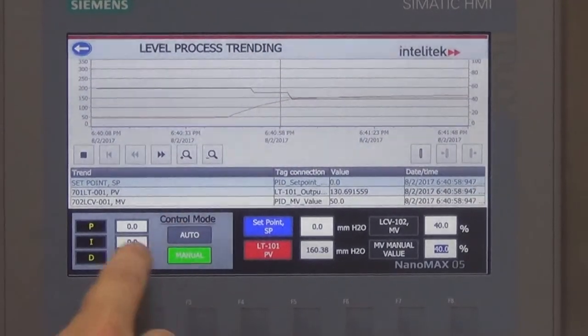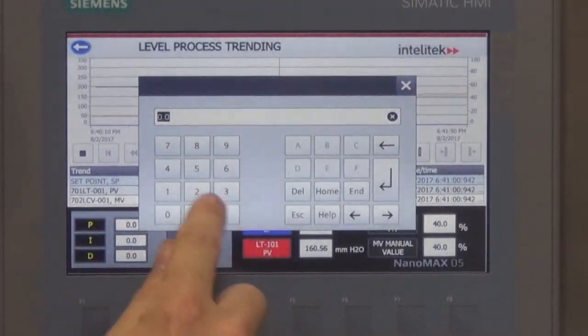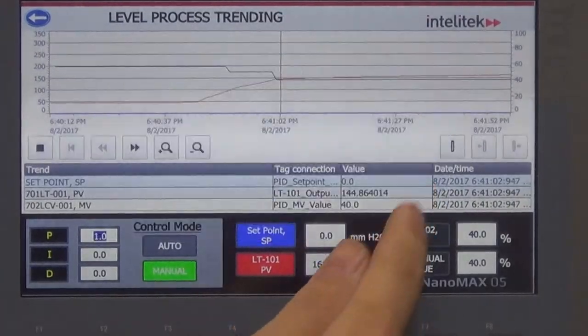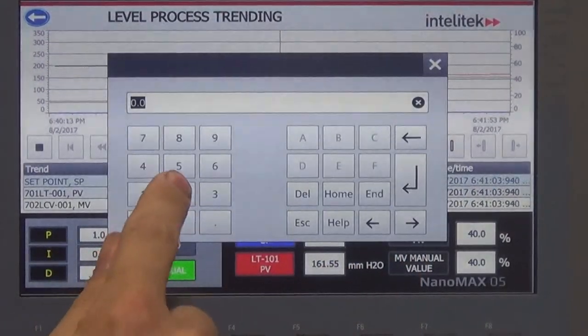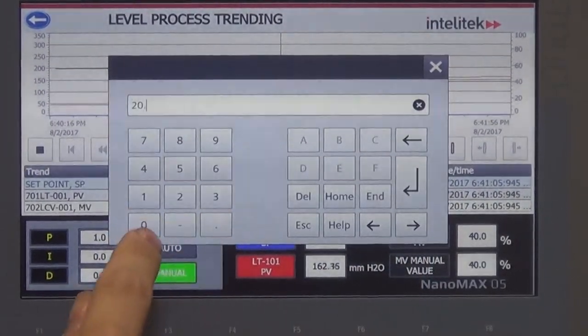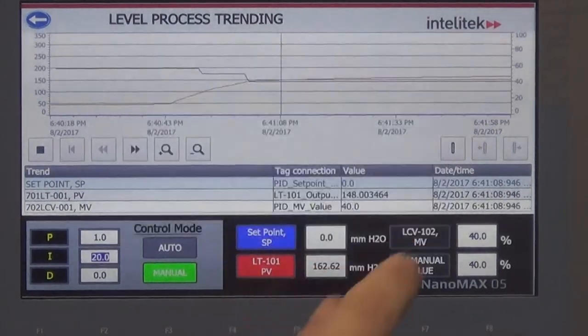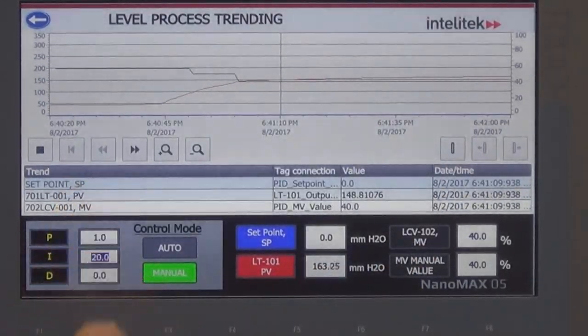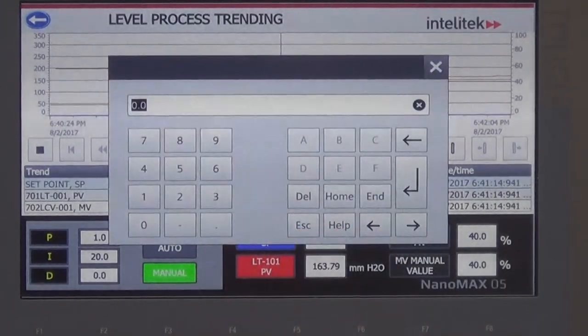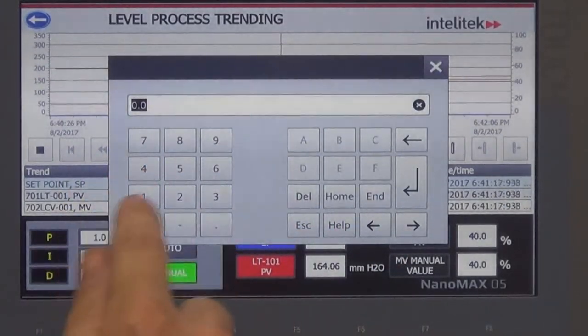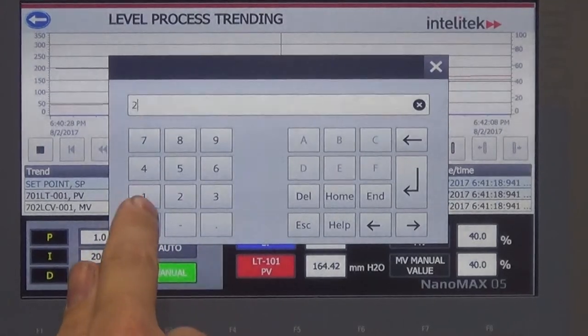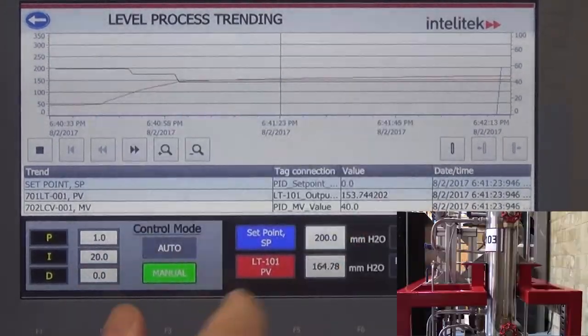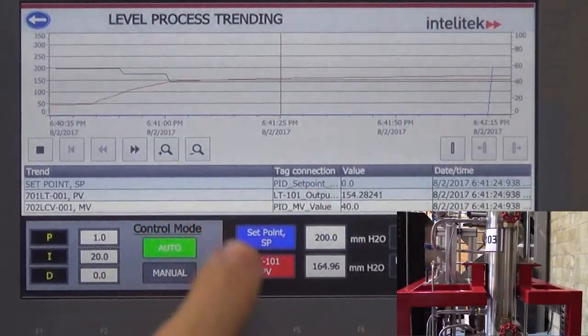And I'm going to type in P, so I'm going to put a value of 1. These are pre-tested values. I have all these values preset in the curriculum. And I got P and I, which I'm going to use. I'm not going to use D in this case. And then I'm going to set a set point of 200. And then I will engage automatic mode.